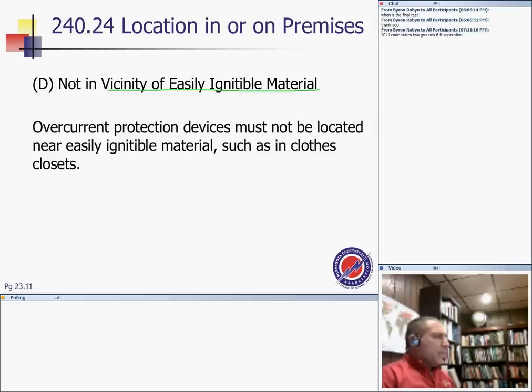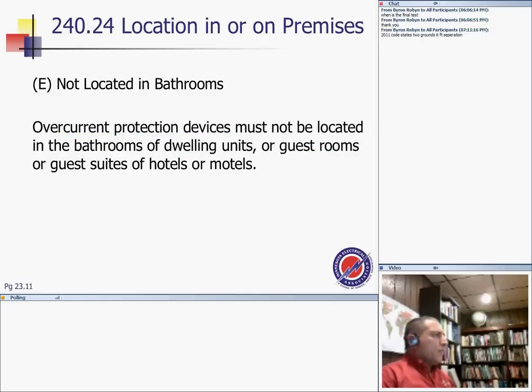You can't put them in a closed closet. If you have an overcurrent device, bathrooms are prohibited in residential. Overcurrent devices must not be located in bathrooms of dwelling units, guest rooms, and guest suites in hotels. If it's a bathroom at the U of M campus in a commercial building, a panel inside that, there's nothing wrong with that.